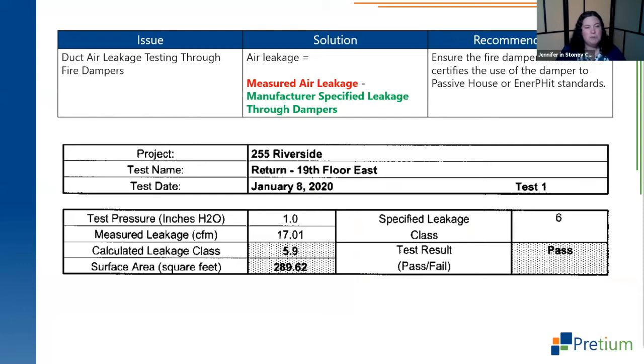Next was an issue we ran into with duct air leakage testing through fire dampers. One thing we found was that this building, obviously, needed a lot of fire dampers. We were creating essentially new penetrations through floor slabs, through fire separations. We were creating new penetrations through wall fire separations from the unit to the corridor. So obviously that meant lots of fire dampers.